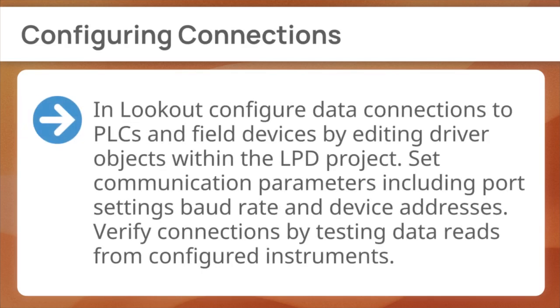Next, configuring connections. In Lookout, configure data connections to PLCs and field devices by editing driver objects within the LPD project. Set communication parameters including port settings, baud rate, and device addresses. Verify connections by testing data reads from configured instruments.